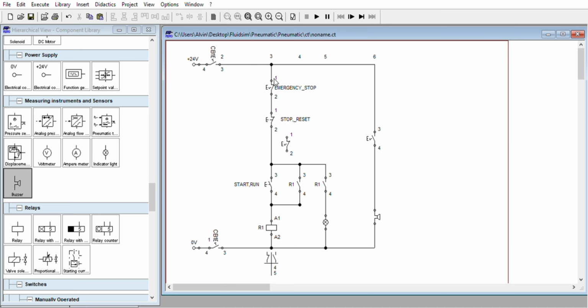And about the 1 and 2 in ISO or IEC standard, 1 and 2 are normally close contacts. See? And 3 and 4 are normally open contacts. In reality, if we have the magnetic contactor, they are labeled 13, 14 in some cases, and the next one, let's say this is 13, 14. This will become 23, 24. Or you just add 10, so it becomes 23, and so on. So if you have another set of normally open contact, it will be 33 and 34.